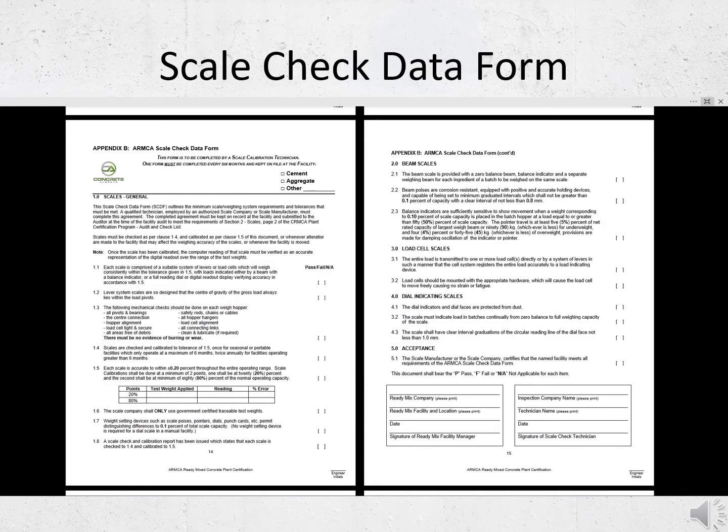While completing the scale inspection and calibration, the scale technician will complete the scale check data form. By signing this document, the technician is certifying the scales meet the requirements of the ARMCA plant certification audit and checklist. The scale check data form must be signed by both the technician and the concrete producer's representative.